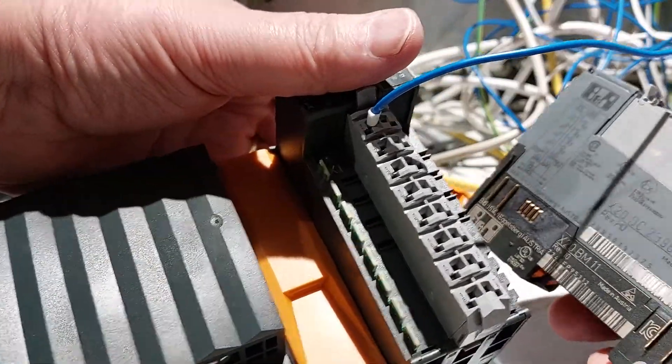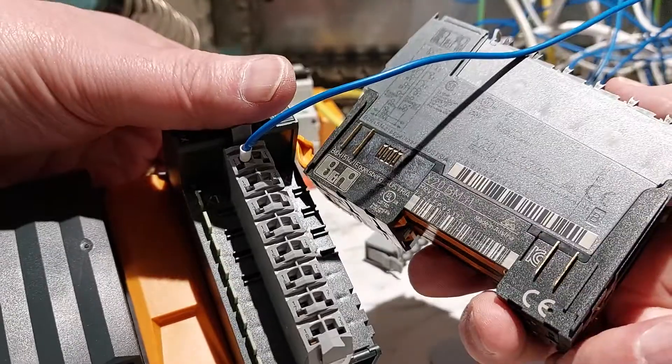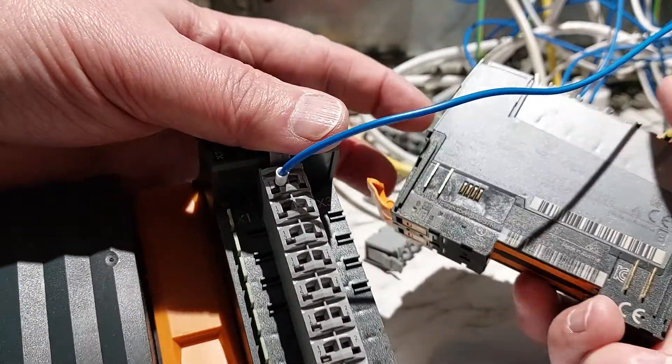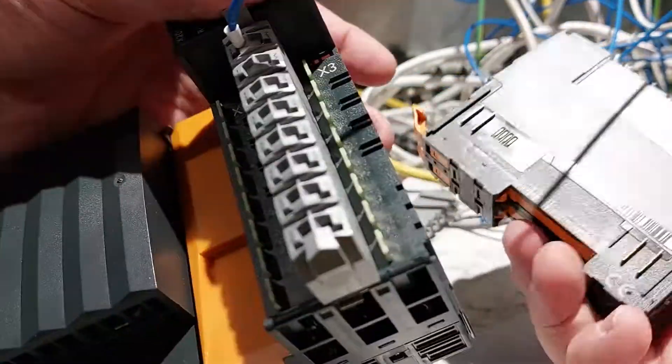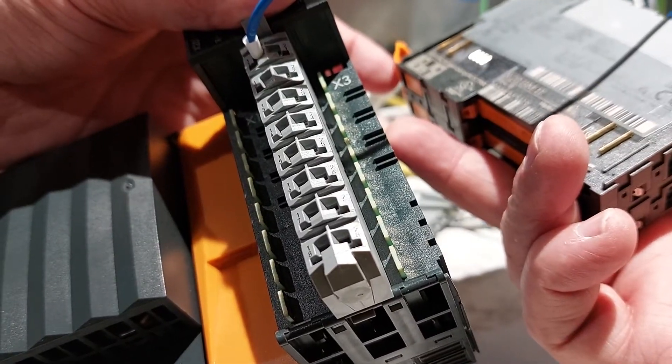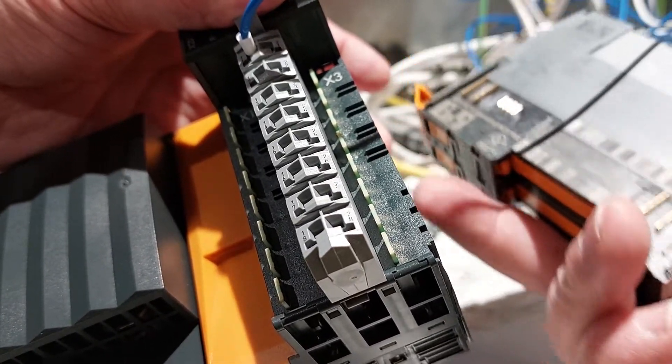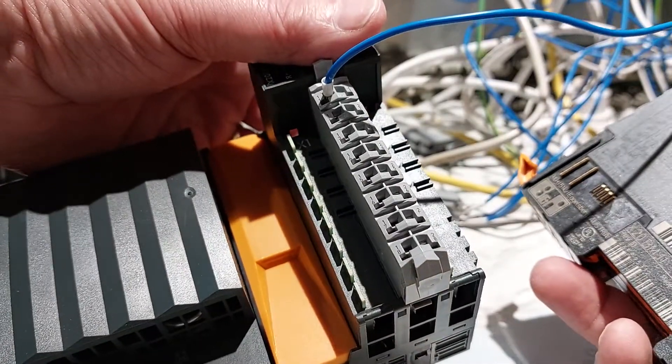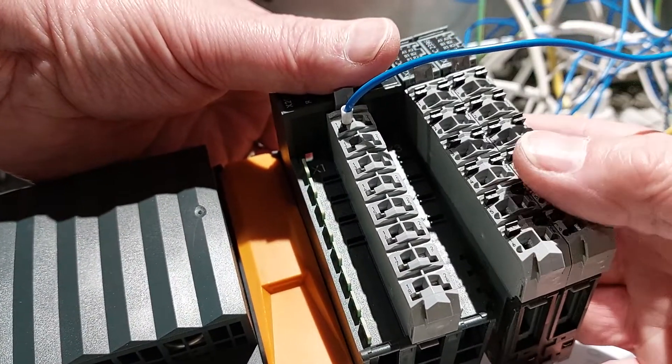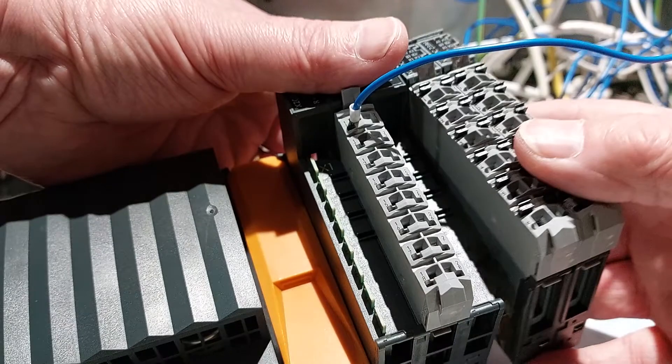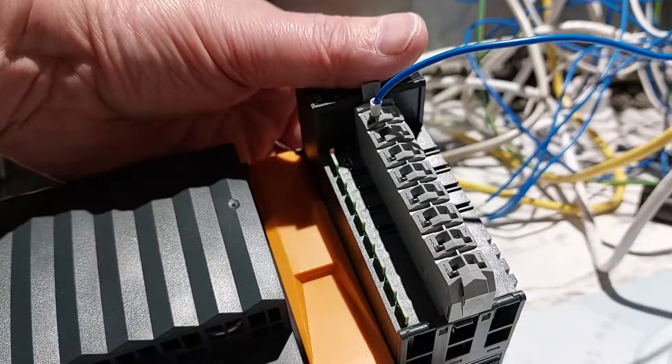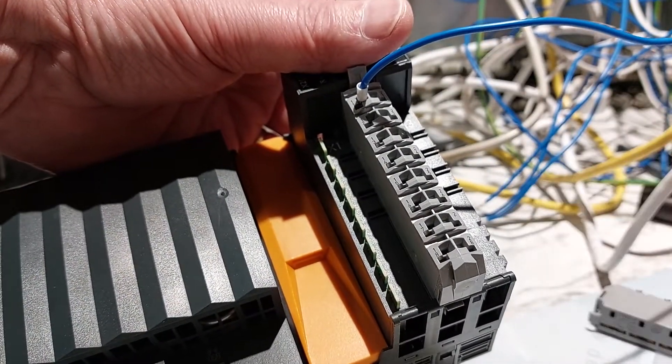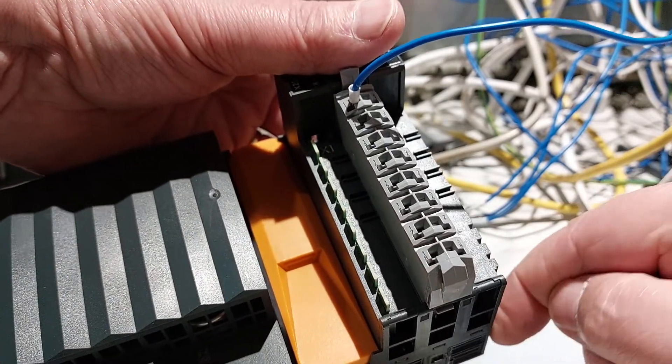So if you take that out there, this bit here comes off and if you force it forward, you can see that they slide into each other. Now you can see along the side here you've got this metal part here. They have to connect with the corresponding slots here and here, and that's what makes the whole connection across the side. Sometimes you can get a module that's attached at the top and kind of loose at the bottom because if you don't actually take the terminal block off, this terminal block blocks this slide here where the two parts engage.